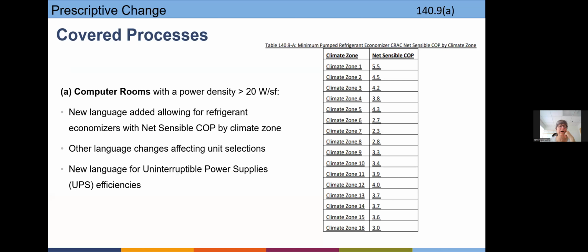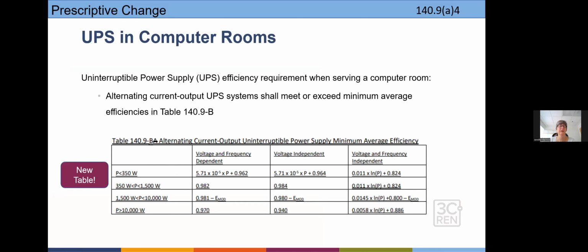For covered processes, the big change is that now whoever is designing those computer rooms - greater than 20 watts per square foot - actually has to look at the climate zone to determine the minimum efficiency or COP on the equipment. There's also some new language for uninterrupted power supplies, and some new equations that go with it.